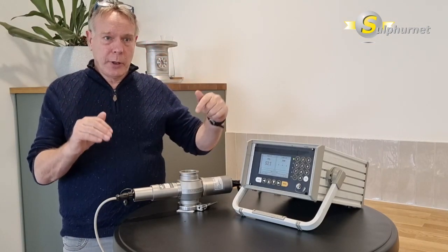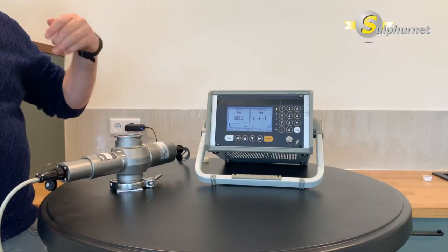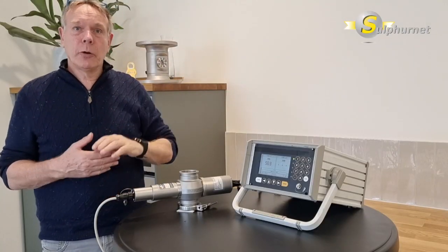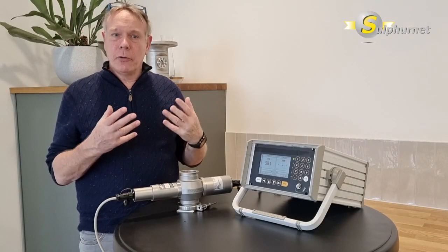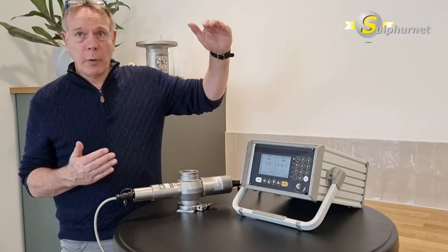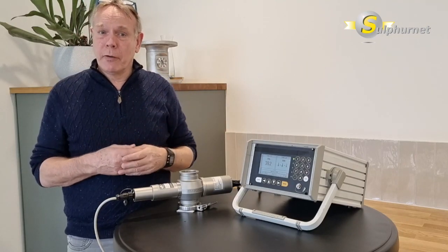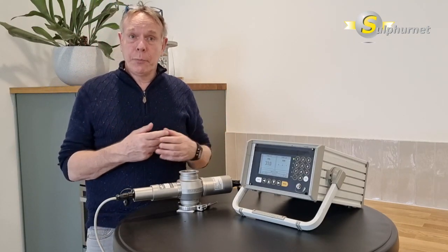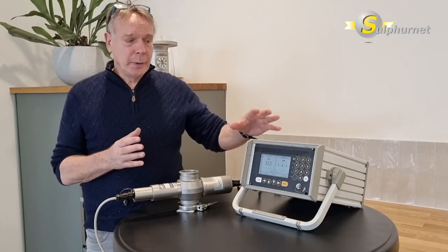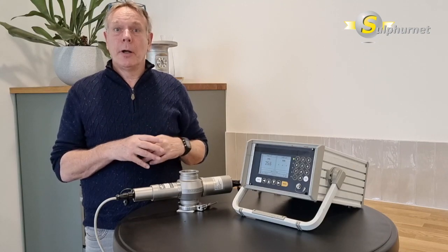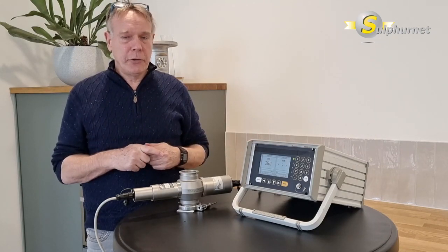This threshold is your limitation that you want to save the process. So this is 70 ppm, which means at 70 ppm you stop the filtration process, or you put the filter in a circulation mode, you get an alarm and you start the cycle, and then you can verify if the number will go down or up, or how it's developing over time, and then you can make a decision to stop the sulfur filtration process. But on the other hand, by measuring this range, you are sure that you're protecting your catalyst bed downstream, and you increase the lifetime of the sulfuric acid plant operation.